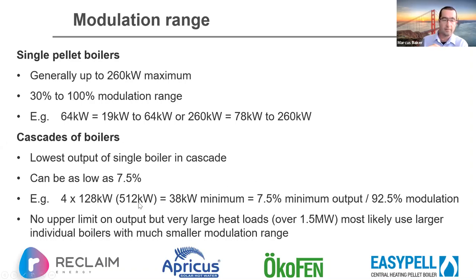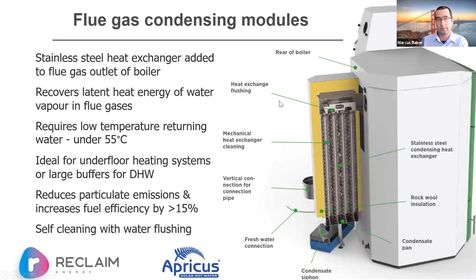Flue gas condensing is available on a few boilers. Ökofen were the pioneers of this technology, where it works very similarly to a gas condensing system — condensing latent heat energy from the water vapor in the flue gases. Cool return water is required to make it work, just as with any gas condensing system.